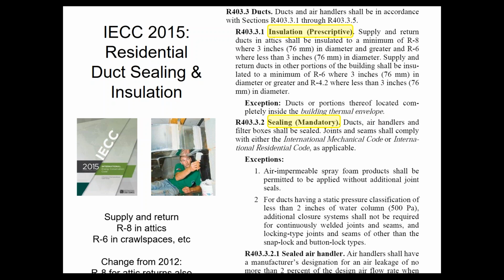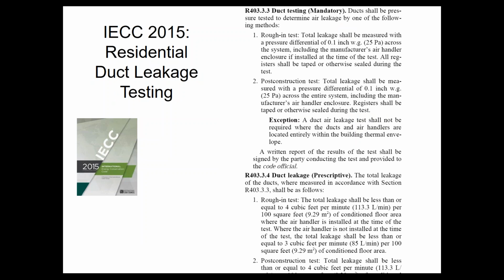Sealing is mandatory. You have to do duct sealing, and it tells you to do it per the IRC or IMC, whichever you're following for your type of project, commercial or residential. You have to do that sealing, but then additionally, you have to do duct testing. So 2012 had this as well. So you guys in Illinois, this is nothing new. You guys in other locations, it might be new to you because some of you guys have skipped, like Wisconsin, skipping the 2012 completely. So if the ductwork is newly installed, new construction or in a retrofit situation, new ductwork, the ductwork would need to be leak tested, pressure tested with a duct blaster.